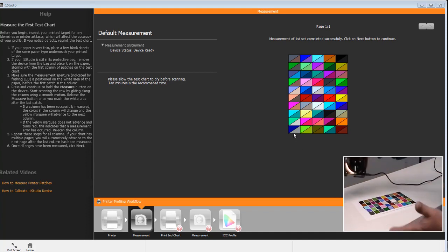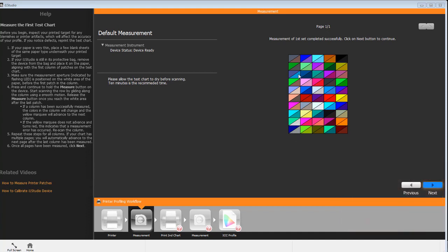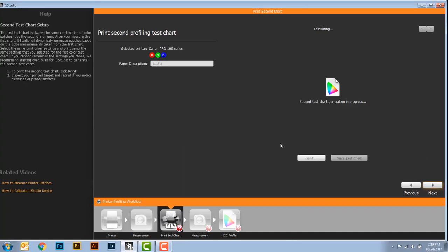The other thing that I'd like to note is that as you start the measurement up the first row, you're going to hear a beep when the device is ready if your sound is turned on. If the measurements are not done correctly, it will beep at you 3 times. So once you have all of these rows completed, we're going to go ahead and click on Next. And then at this point, based on the measurements of the first test chart, the second test chart generation will be in progress. And this is where you're going to be prompted to print out your second chart.